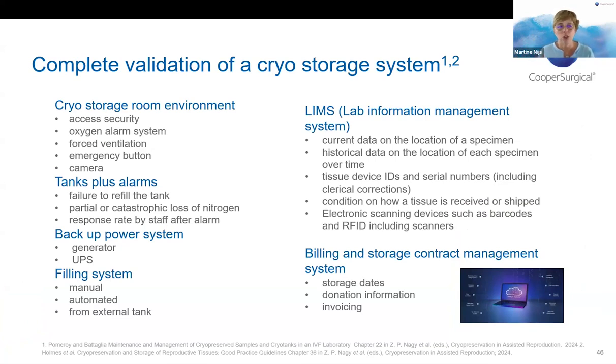This is your cryo storage environment. So it's not only the dewars, it's also your security access that you need to validate, your oxygen alarms, your forced ventilation. Create situations that are alarming and check if that really works. The emergency button, you have to validate that it's doing what it's supposed to do when there is an oxygen alarm, for example, or when you are in need of help. The tank alarms we discussed right now, so you have to check those as well. And then your backup system: of course, you need to check if the generator will switch on, because you need that for your forced ventilation. And if you have a UPS system, you also have to do that at least once a year.